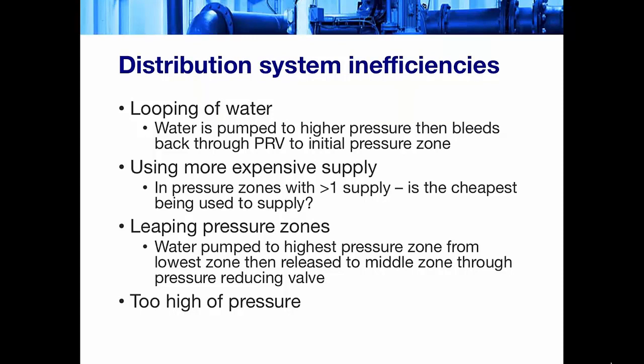So there's some relatively common distribution system inefficiencies out there. The first of which can be described as looping of water. So this is not the elimination of dead-end pipes in our distribution networks by connecting two dead ends and allowing water to flow freely within the system. This is when water is being pumped to a higher pressure zone and then bleeds back through a pressure reducing valve to the initial pressure zone. So basically, in this scenario, you're running a pump, sending water uphill, and then it comes back down through a pressure reducing valve to the initial pressure zone. That is just wasted energy. Sometimes it's probably justified as a way to maintain water quality in one or both of the pressure zones. But it's a pretty expensive way to maintain that water quality because you're just burning up energy.